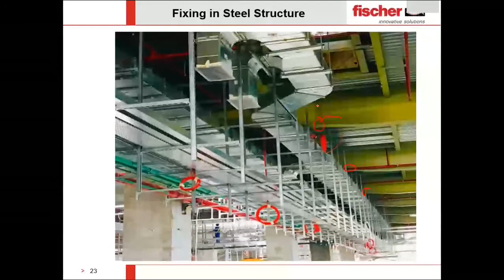So this covers things from the anchor point of view. Now, coming to the second part, which is the rod. This rod is affected based on the type of support—we don't always need a rod. The most common type used for MEP is suspended, because it's just suspended from the top, from the ceiling, with a rod. But it's not limited to that; it can also be suspended, but not with a threaded rod—it can be suspended with channels.